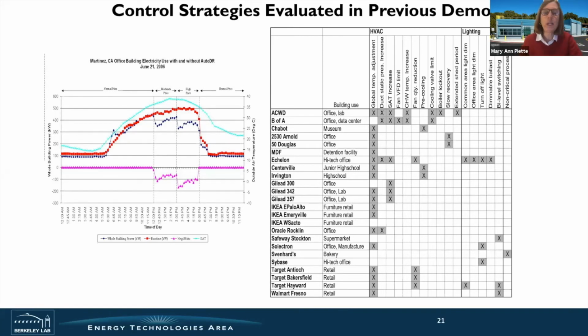We reset the thermostat twice. Typically the building's running at 70, and you might go from 70 to 75 or 74, and the VAV boxes go to minimum and the chiller backs off. We get some shed because we're running the building at a warmer temperature for a couple of hours.